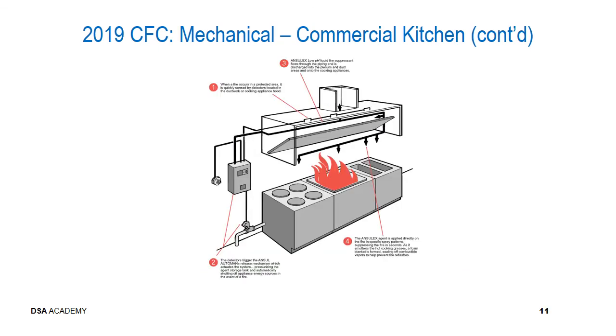Here's a depiction of a traditional commercial kitchen system. We have the appliances below the Type 1 exhaust hood, the fire suppression system noted on the left and the manual pull station, the agent distribution piping throughout the hood with nozzles protecting the exhaust ductwork, the plenum area above the filters, and the appliances below.